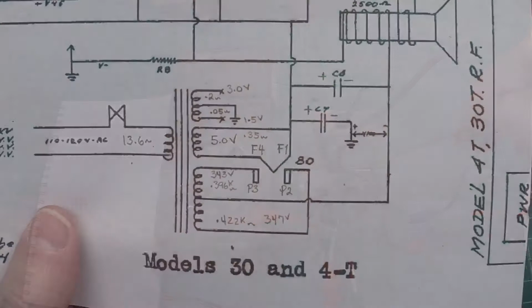Also, one of my great subscribers, someone who follows along, reminded me that on more than one occasion I failed to test between all the conductors and the frame of the transformer. So if you're out there testing transformers, be sure when you're doing your DC measurements, etc., that you make certain there's no resistance between any of your leads and the bell housing, unless it's tied to a known ground location.